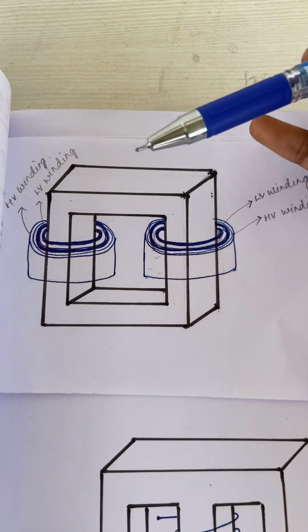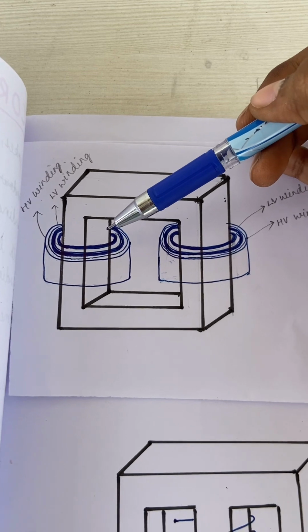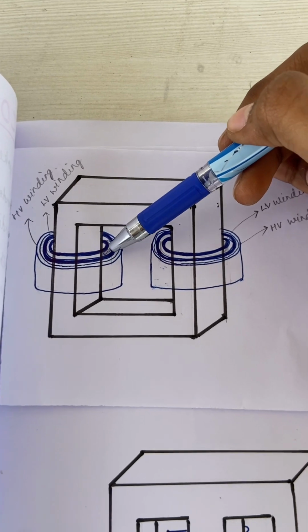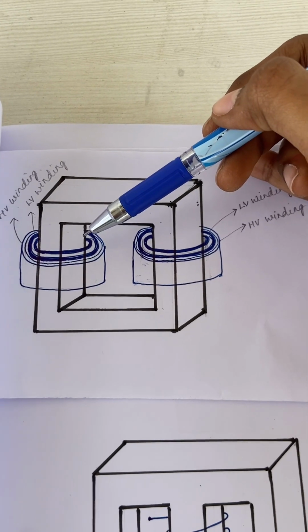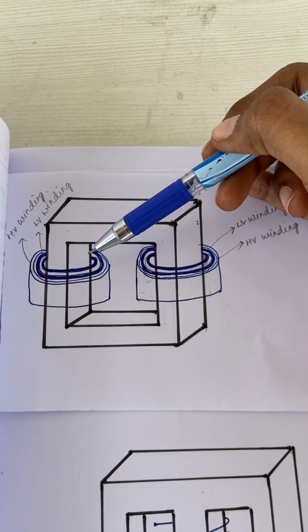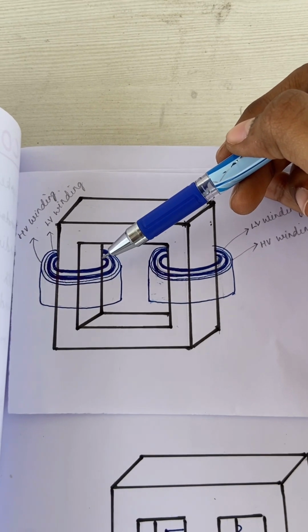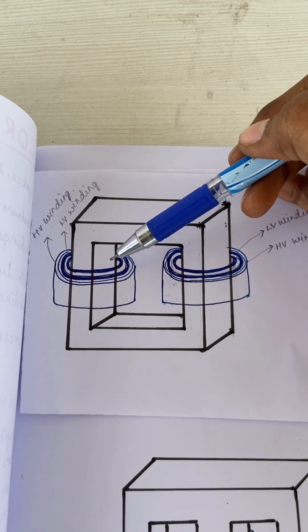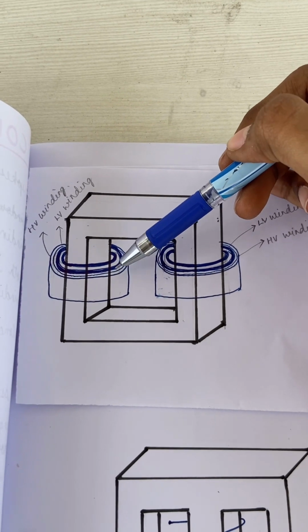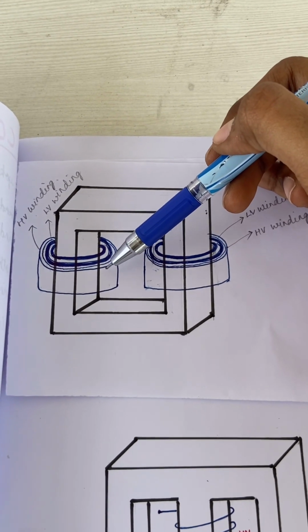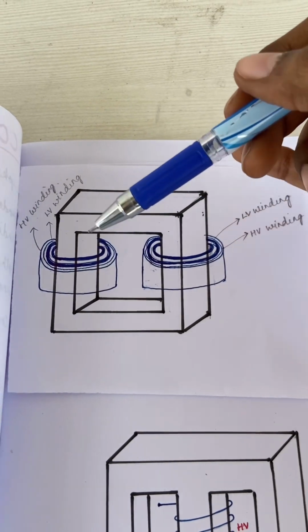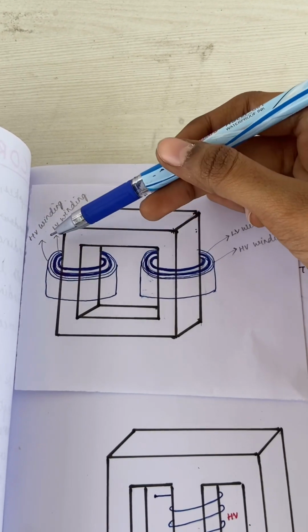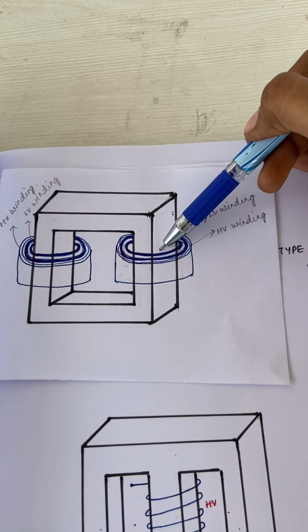Why do we do that? It is because of insulation. Actually if we wind LV directly to the core, we will have less insulation requirement. There is one more reason, that can be explained later. So first we'll be concentrating on this. If we wind LV directly to the core, the insulation requirement will be less, and over the LV winding, if we wind the HV winding, then the insulation required between LV and HV winding will be less. So we'll be using it like this. That is, there will be a core, on that core we wind LV, and over that LV winding we wind HV. Similarly, on the other limb also the same process takes place.